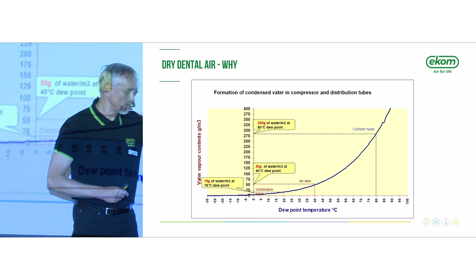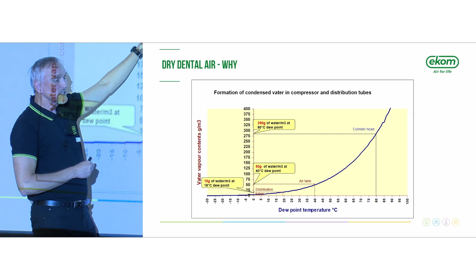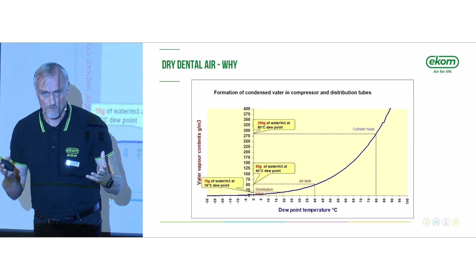And this is the content of water vapor present at each temperature point, considering the air is saturated. So from the head of the compressor, the air temperature is about 80 degrees Celsius. Look at that - it can contain about 290 grams of water vapor per cubic meter.